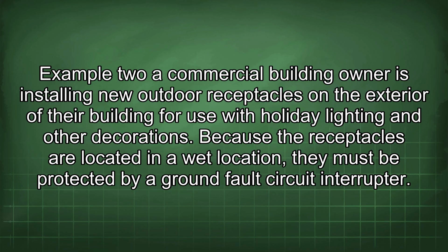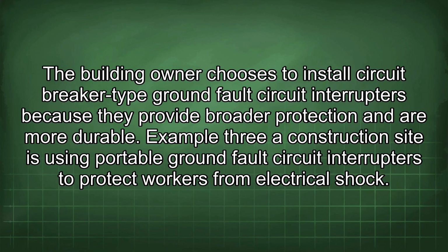Example 2. A commercial building owner is installing new outdoor receptacles on the exterior of their building for use with holiday lighting and other decorations. Because the receptacles are located in a wet location, they must be protected by a ground fault circuit interrupter. The building owner chooses to install circuit breaker type ground fault circuit interrupters because they provide broader protection and are more durable.